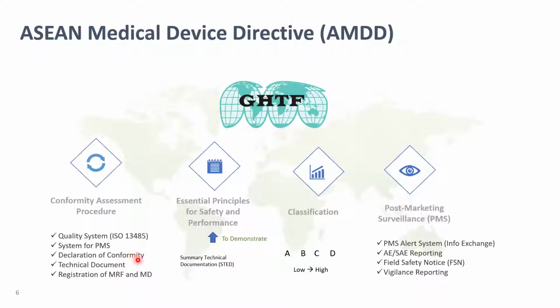We also need to provide a declaration of conformity to ensure our products are following harmonized international standards. The other essential document is what we call the essential principles for safety and performance. Most of the authority reviewers will start from this document. According to this document and also the risk management report, the reviewer will further refer to the technical document, which is the STED explained in the GHTF guidance. And the classification in the GHTF guidance is Class A to Class D, from the lowest to highest. There is also a lot of guidance about post-market surveillance.